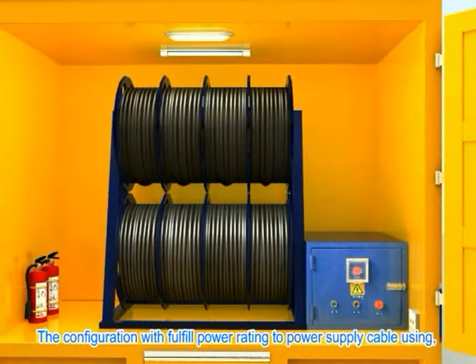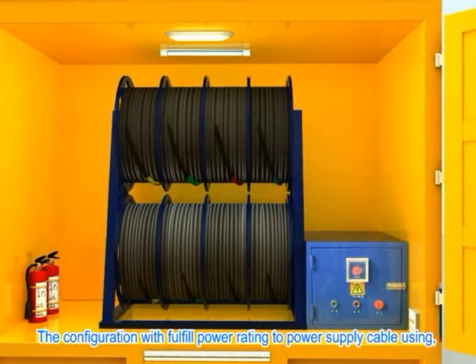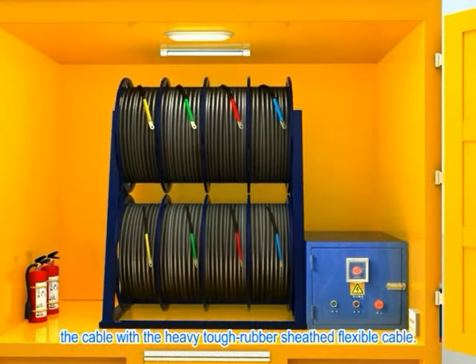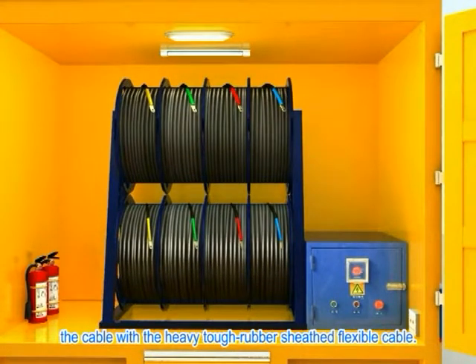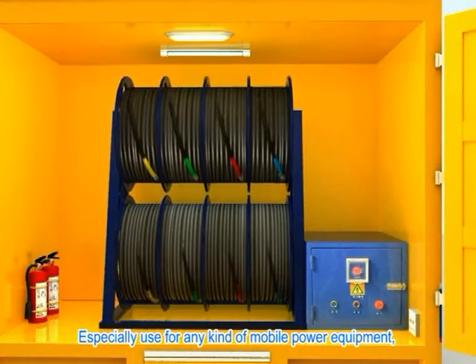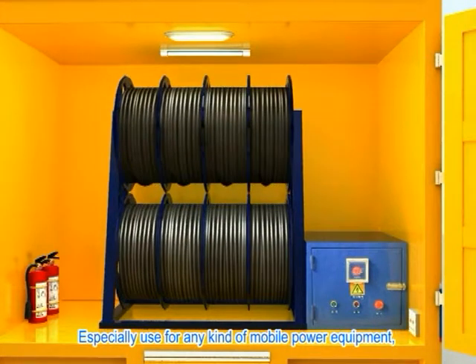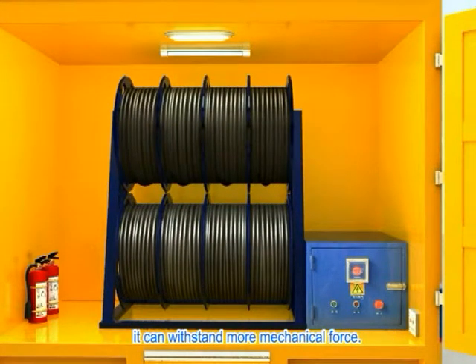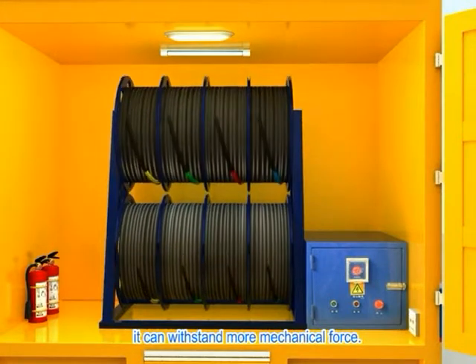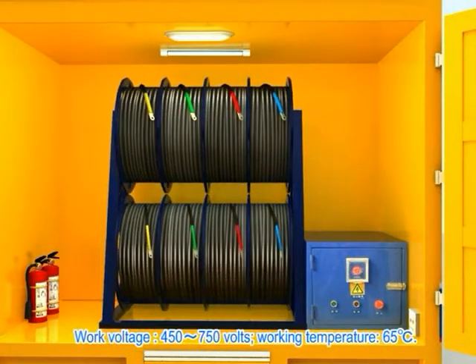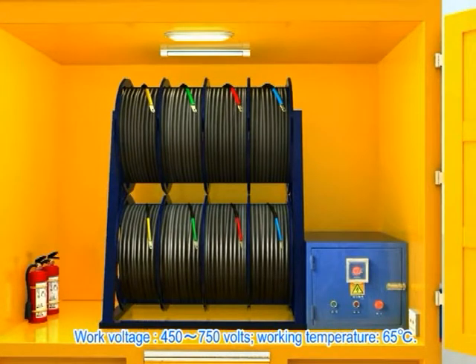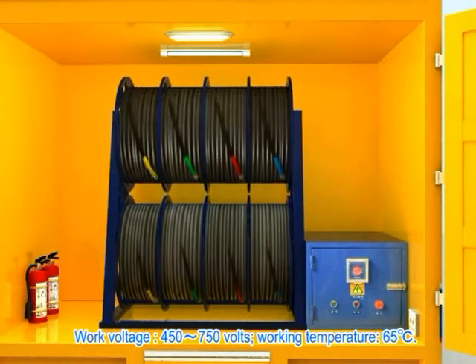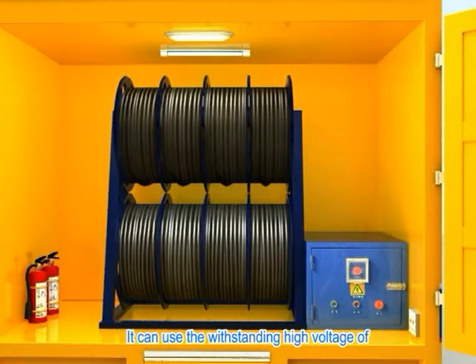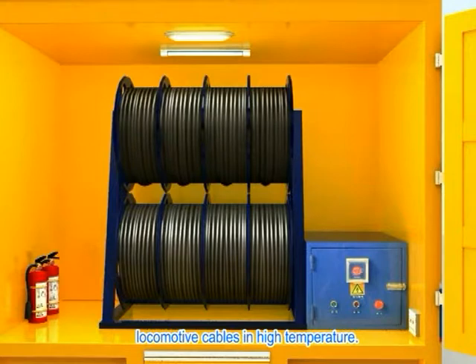The configuration comes with full rated power supply cable. The cable is a heavy-duty rubber sheathed flexible cable, especially used for any kind of mobile power equipment. It can withstand more mechanical force. Working voltage 450 to 750 volts. Working temperature 65 degrees. It can be used as a high voltage withstanding locomotive cable in high temperature.